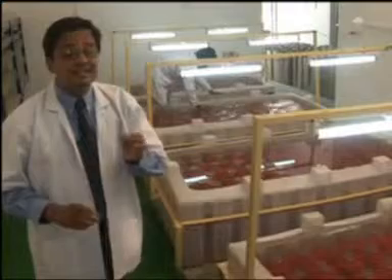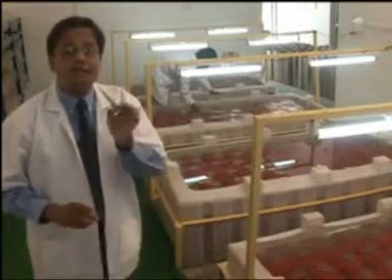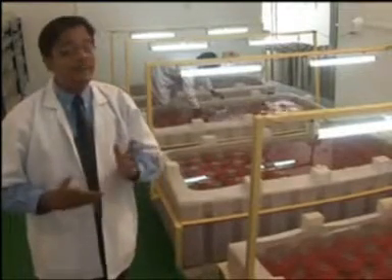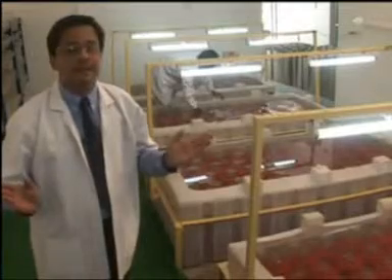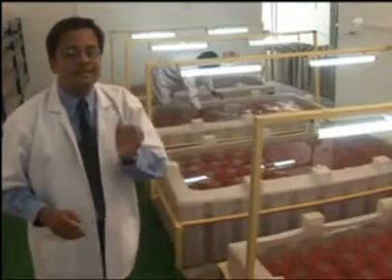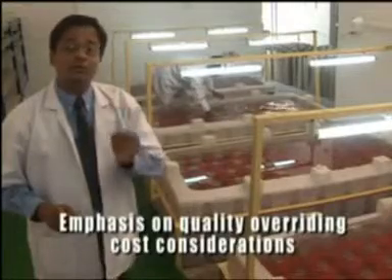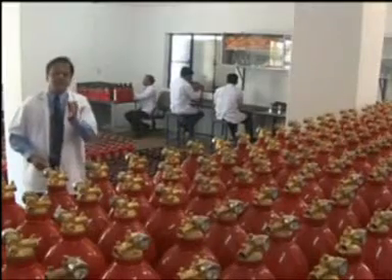The third and final test involves activating 1.5% of all finished extinguishers selected at random. Consider the cost implications: 1.5% of all ready extinguishers in each batch are activated, thereby rendering them entirely useless for sale. This is yet another prime example of emphasis on quality overriding cost considerations. Finally, every ceasefire ABC extinguisher carries the independent quality certifications of ISI, ISO 9001, and the Conformité Européenne or CE mark.